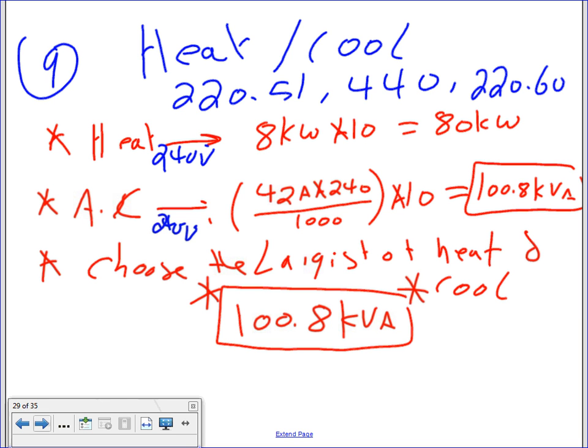Yes, you divide it by 1,000, because of all the calculation that we're doing. So in order to convert it, otherwise you'll be adding cents to dollars. 10 cents plus $10 are not 20. 20 what? Cents and dollars. You see what I mean? That's why we divide by 1,000 immediately. Because volt-amps don't mean much when you size for buildings. It's always kVA, because buildings are big loads.